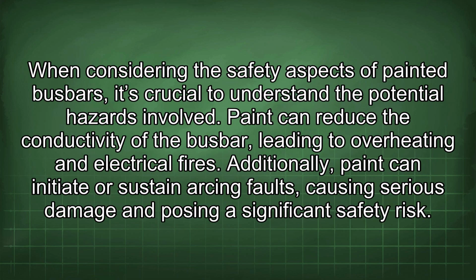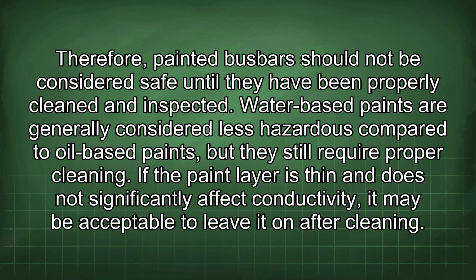When considering the safety aspects of painted busbars, it's crucial to understand the potential hazards involved. Paint can reduce the conductivity of the busbar, leading to overheating and electrical fires. Additionally, paint can initiate or sustain arcing faults, causing serious damage and posing a significant safety risk. Therefore, painted busbars should not be considered safe until they have been properly cleaned and inspected.